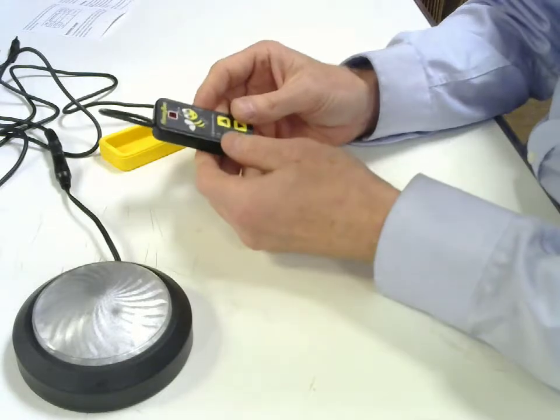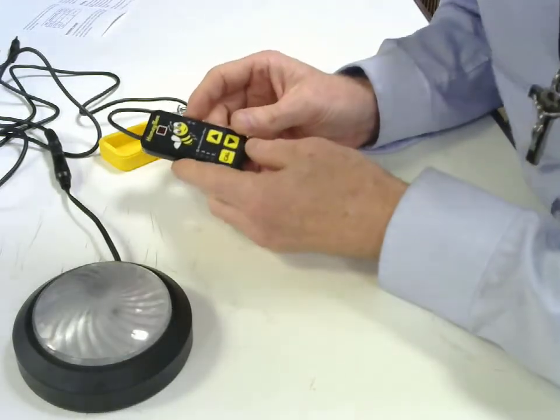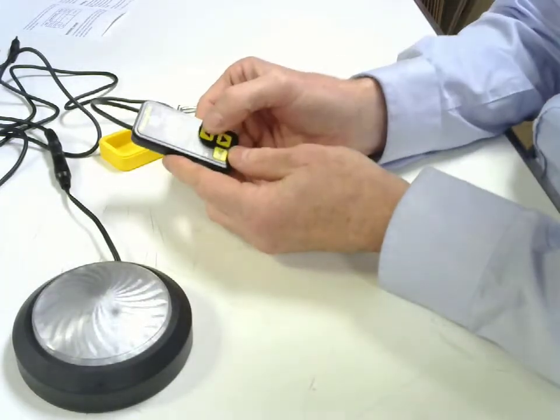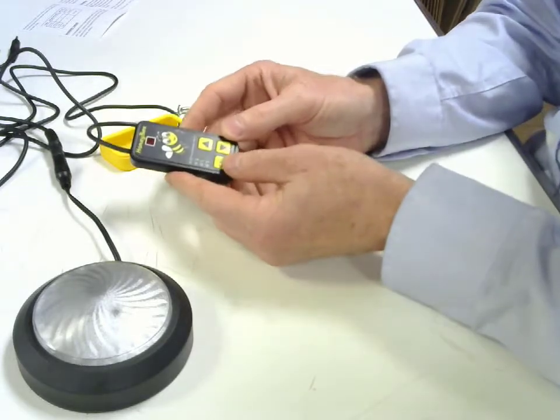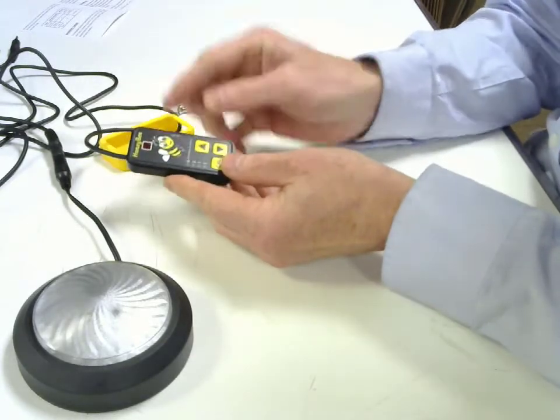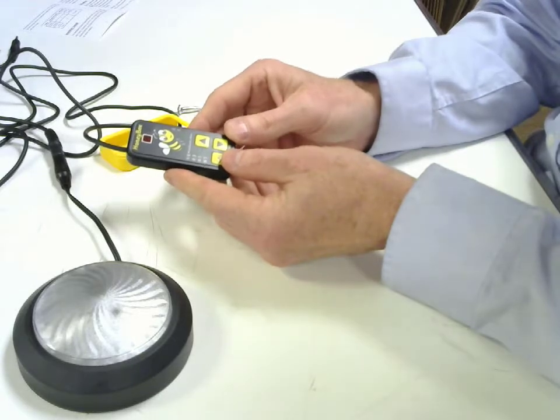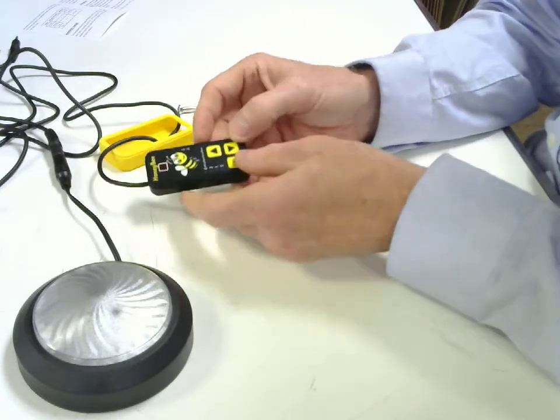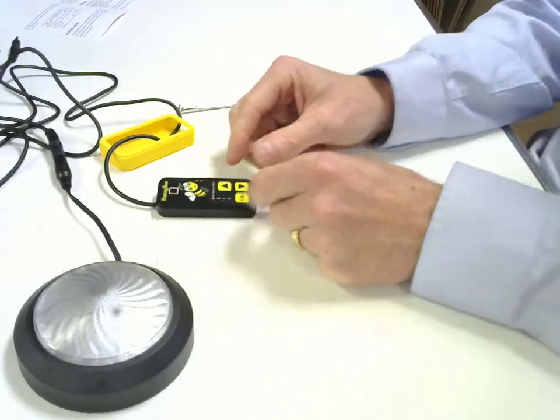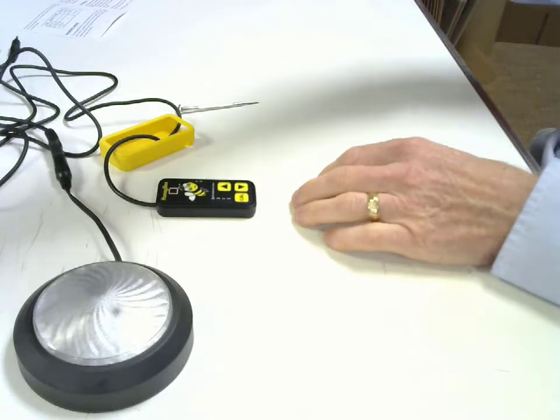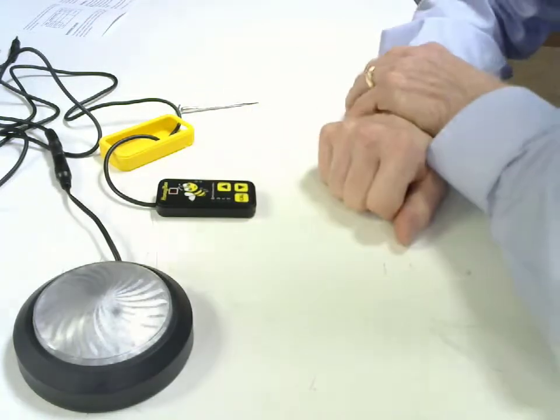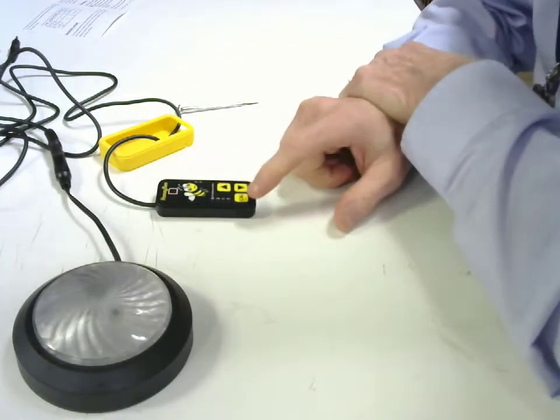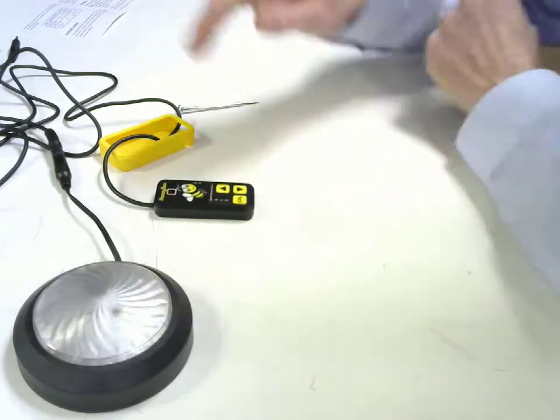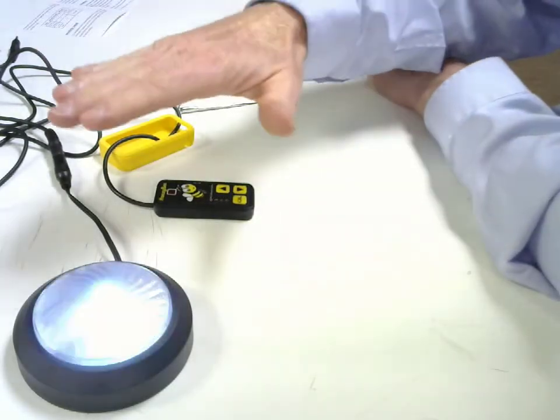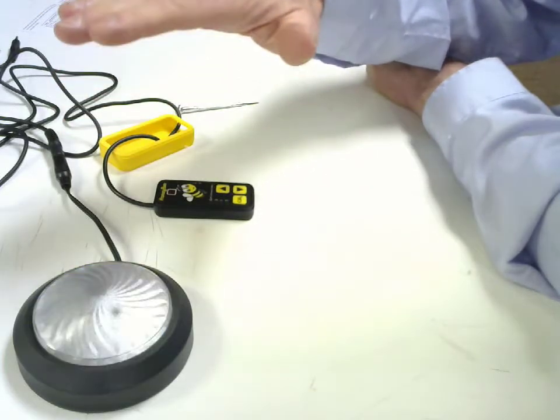That's a problem. So please remember, when you turn this device on, when you change range, or when you press the calibrate button, no fingers near this little red switch, nothing. Whatever you're going to use as an activation object, keep clear of this. I would suggest at least a good foot away. Because again, the HoneyBee needs to know what an empty universe looks like. So let's just recalibrate it on the 6-inch range without my hand in the way. And now look, we're back to great functionality again. Okay?